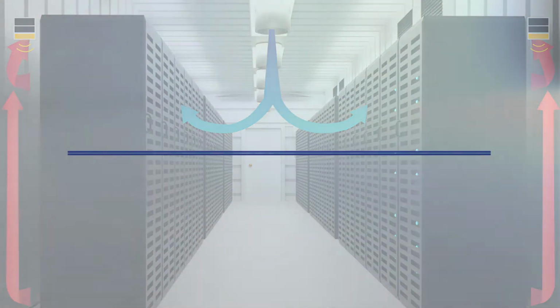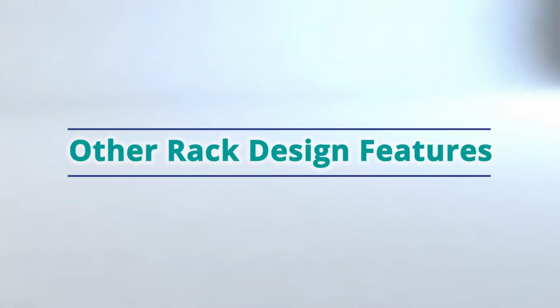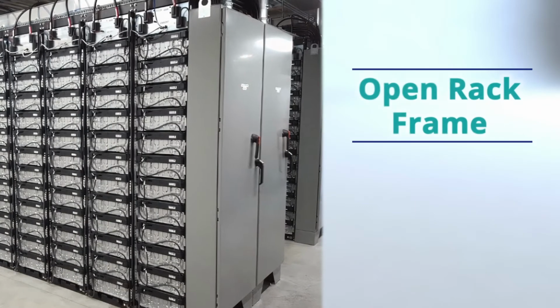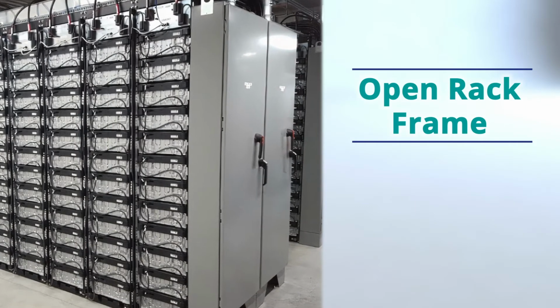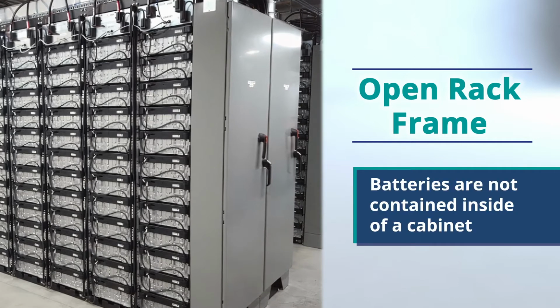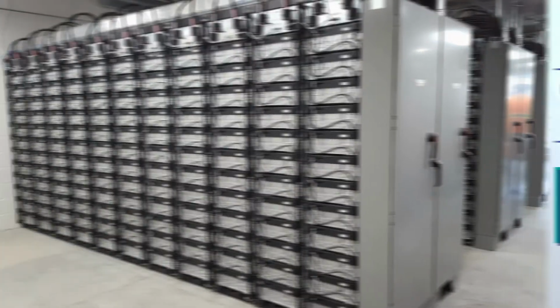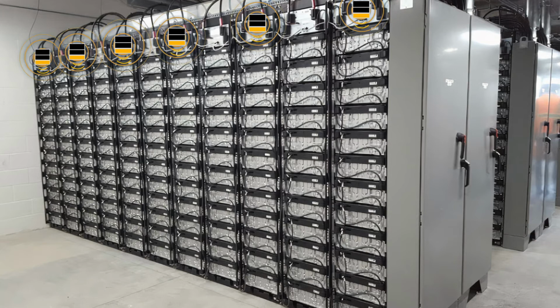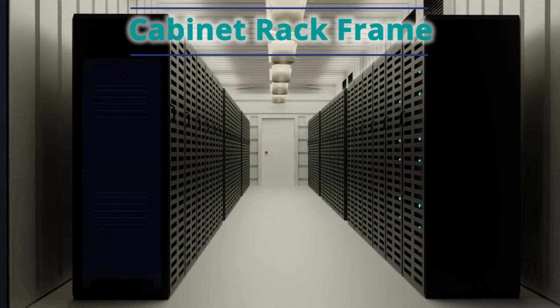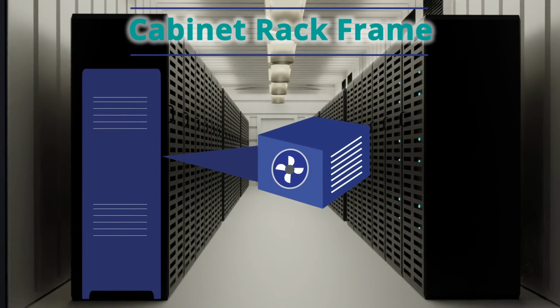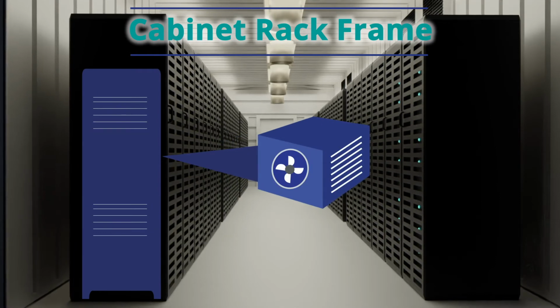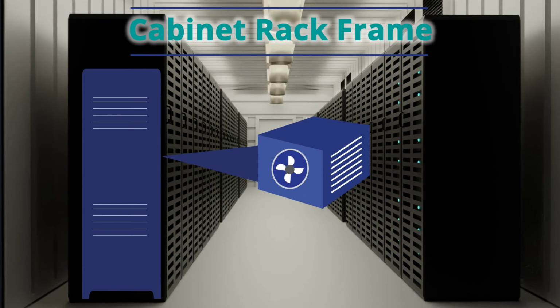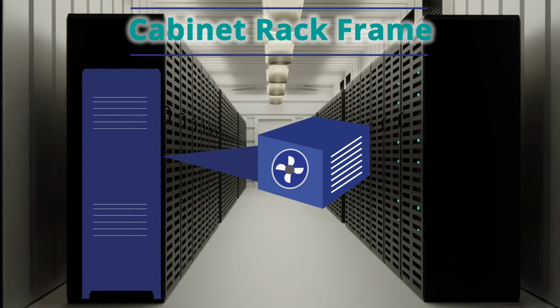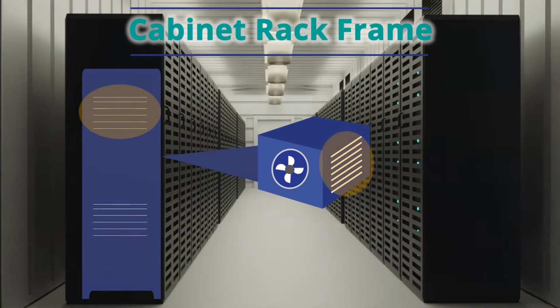We look beyond airflow patterns at several other rack design features for sensor reductions. An open rack frame. If the battery rack frame is open, batteries are not contained in a cabinet. Then usually we use one monitoring sensor for every 2 battery racks. Cabinet rack frame. If the battery modules are contained within a cabinet, no sensor reductions can happen unless other conditions are met, such as the presence of module or rack vents.